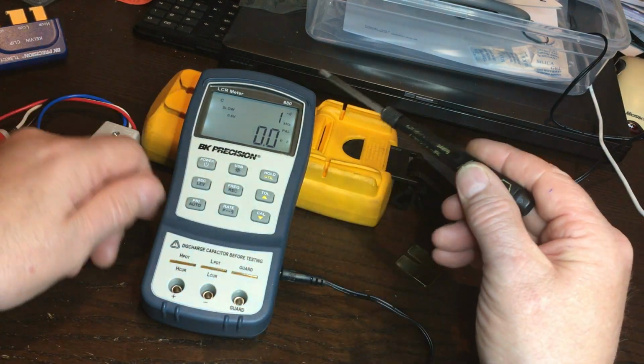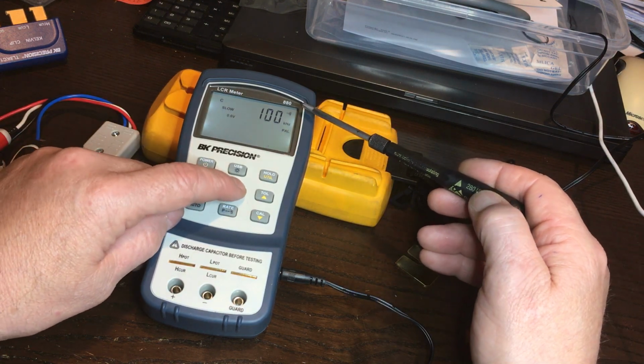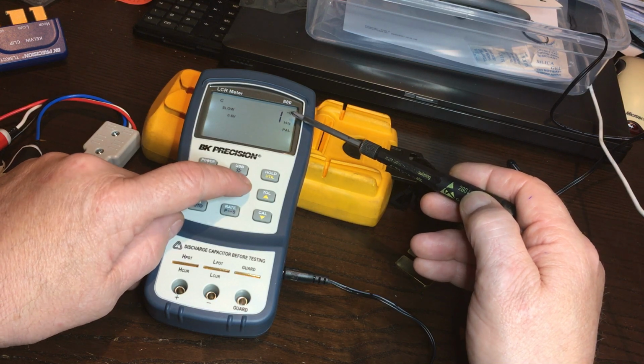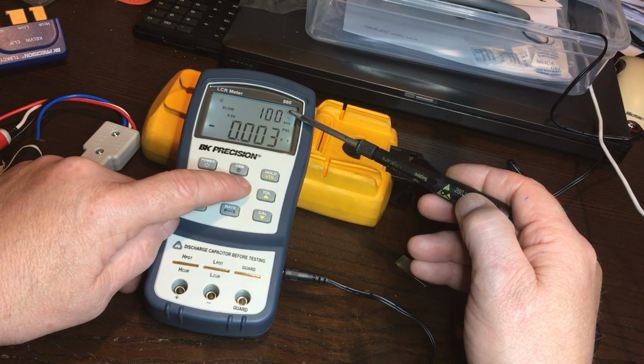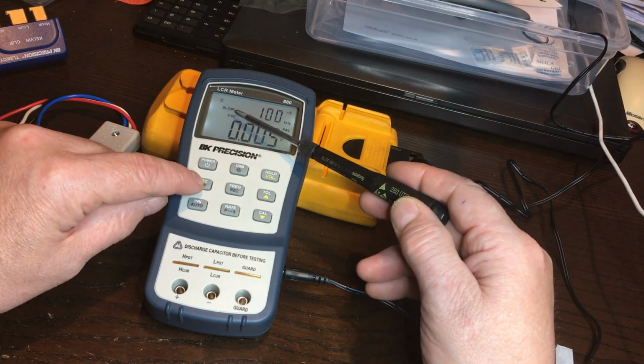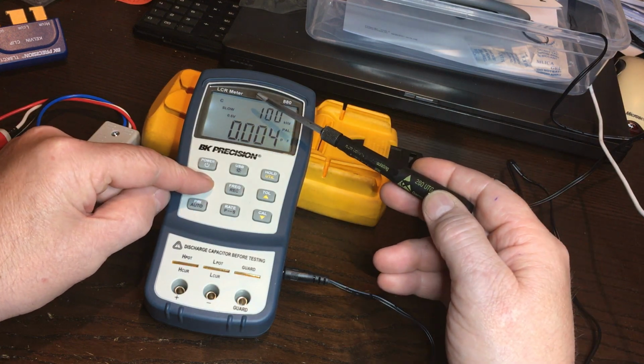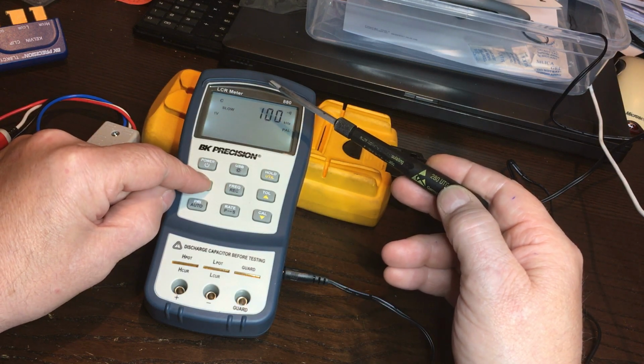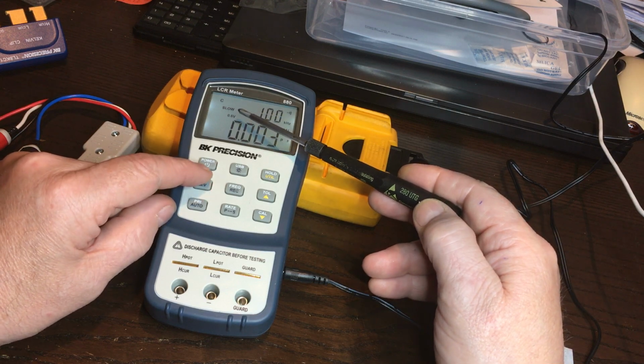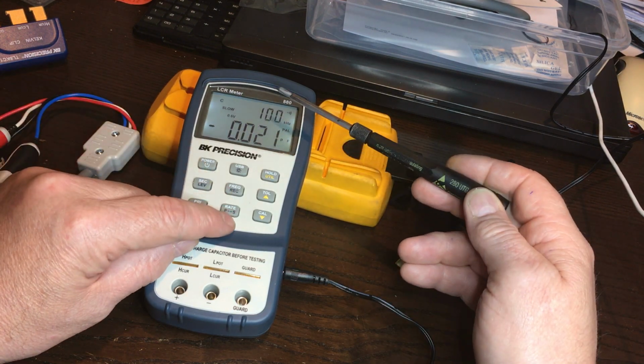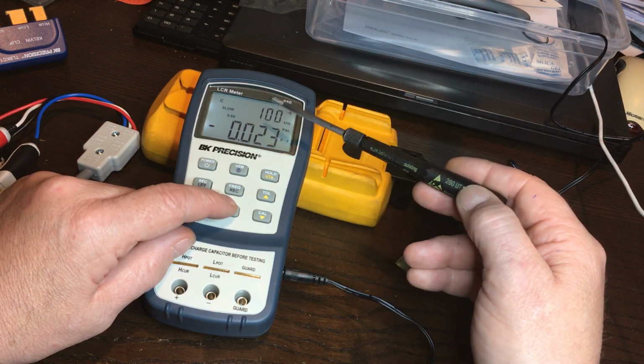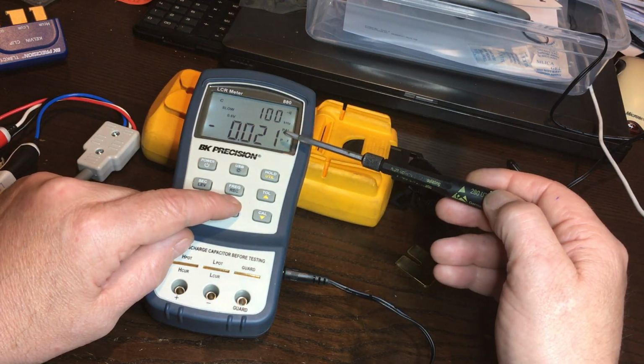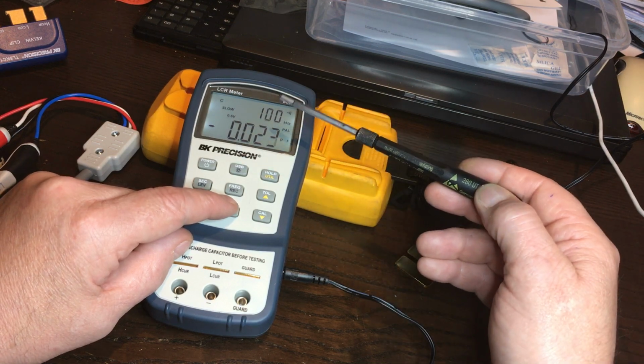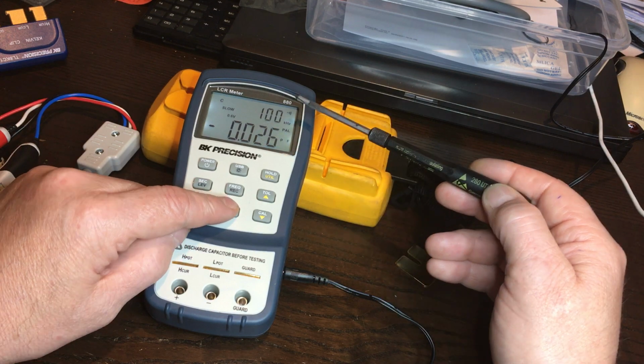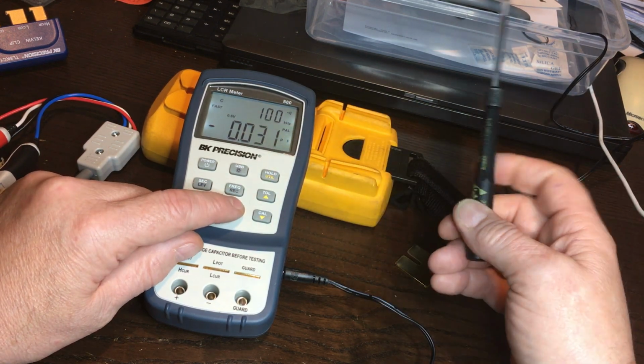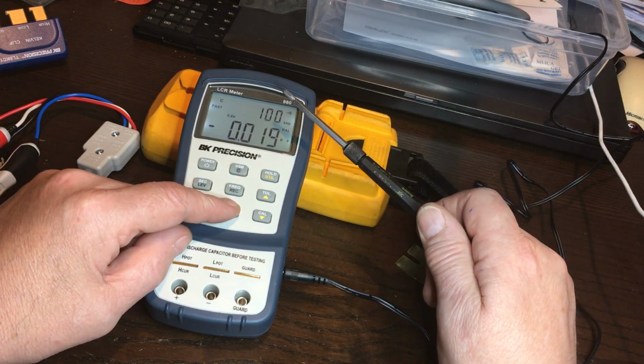In that case, you can change the measurement frequency from, let's go to the beginning, 100 Hertz, 120 Hertz, 1 kilohertz, 10 kilohertz, and 100 kilohertz. You can change the measurement voltage level from 0.3 volt to 1 volt to 0.6 volt, which is the standard. You can change the measurement rate, the refresh rate, or the measurement interval from slow, in which it has a nice display. It's still, you can see 23, 22, 23, 22, 21. But if you put it on fast, it goes berserk. I think this is not necessary, but hey, it's there. Maybe you got a need for that.